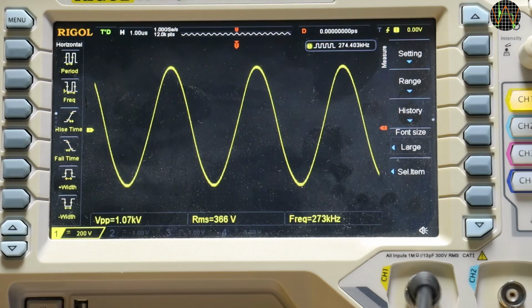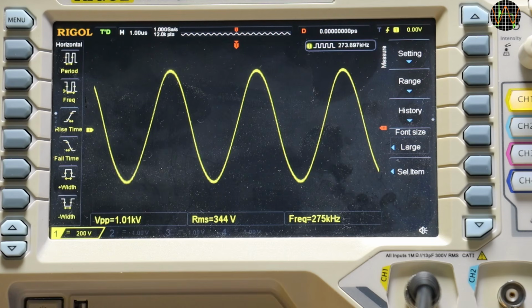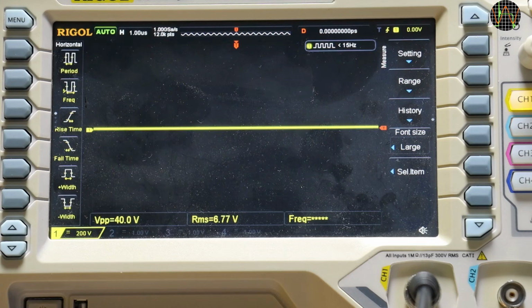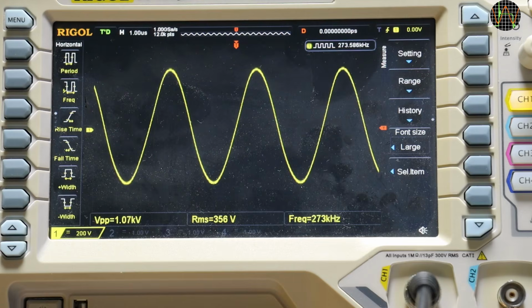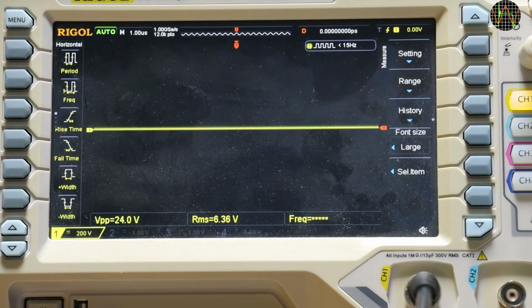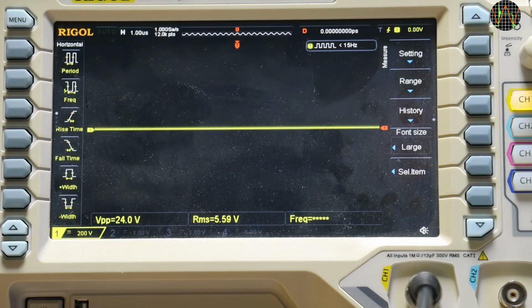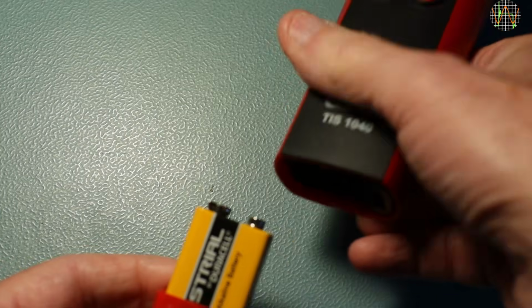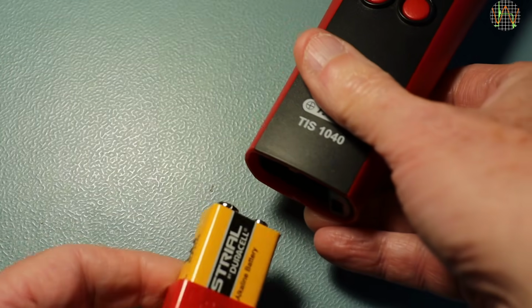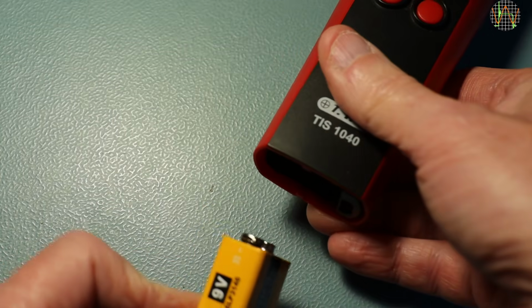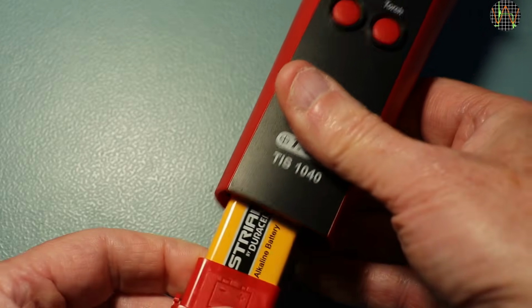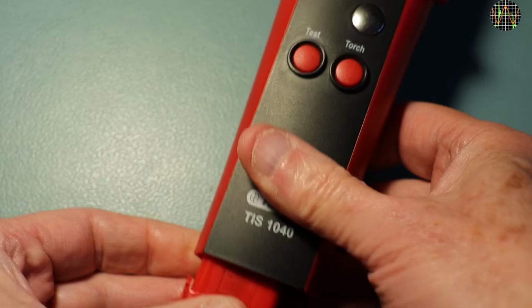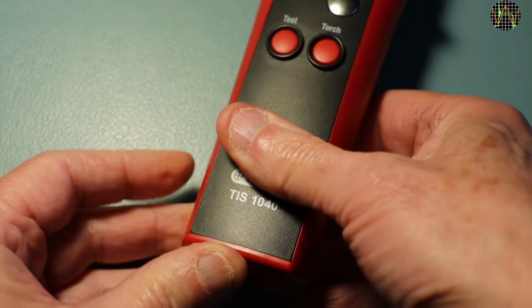A nice sine wave with a peak voltage of 1.11 kilovolts and a frequency of 275 kilohertz. The voltage is a bit lower than expected, but the manual states that the 3 kilovolts are only with a fresh battery, and this battery came with the tester when I bought it, and it's certainly not fresh. And speaking of the battery, this compartment is the only thing that's accessible in this tester. The battery sits in this little bottom piece and is inserted into the tester and locked in place.